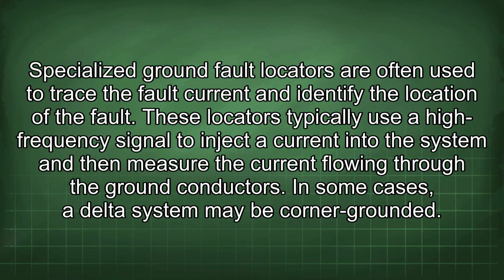Specialized ground fault locators are often used to trace the fault current and identify the location of the fault. These locators typically use a high-frequency signal to inject a current into the system and then measure the current flowing through the ground conductors. In some cases, a delta system may be corner-grounded.